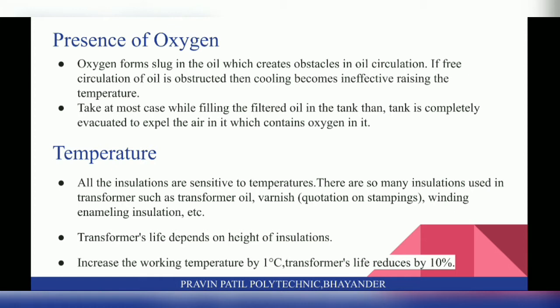Presence of Oxygen: Oxygen forms sludge in the oil which creates obstacles in oil circulation. If free circulation of oil is obstructed then cooling becomes ineffective, raising the temperature. Take utmost care while filling filtered oil in the tank — the tank is completely evacuated to expel the air in it which contains oxygen.